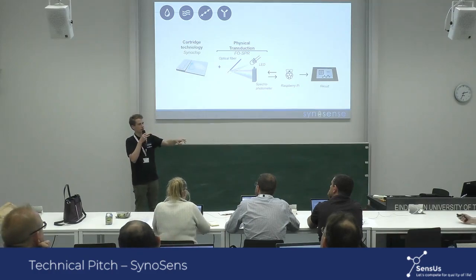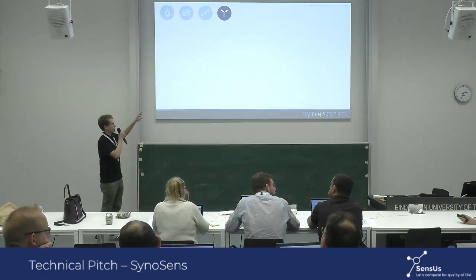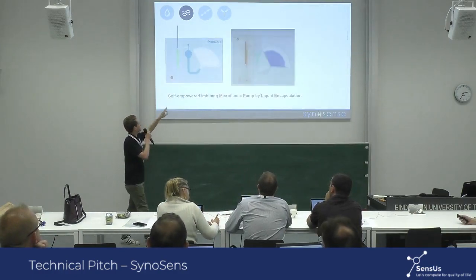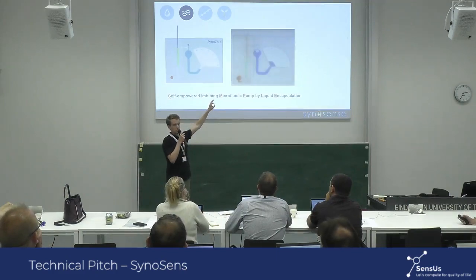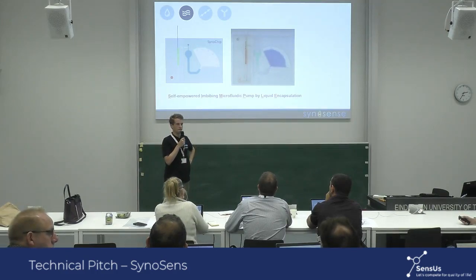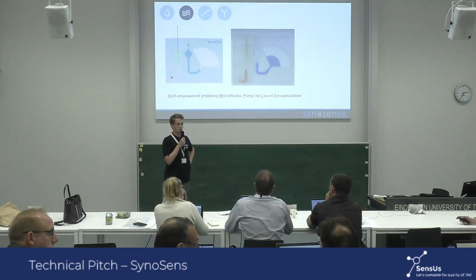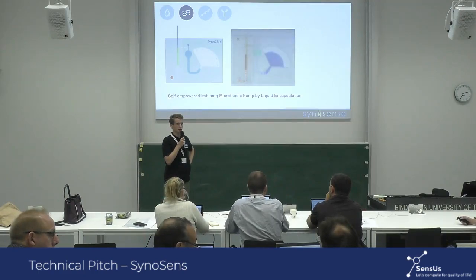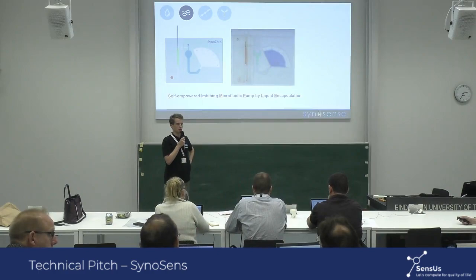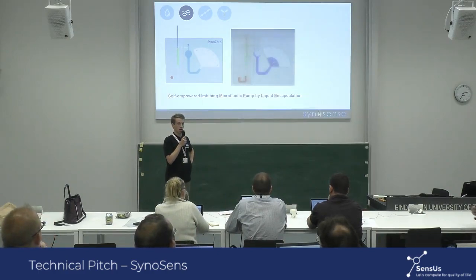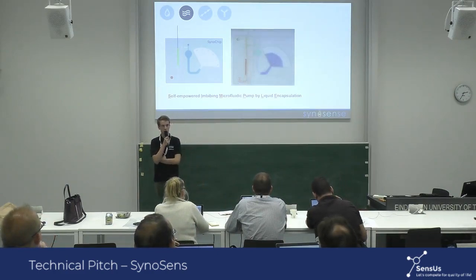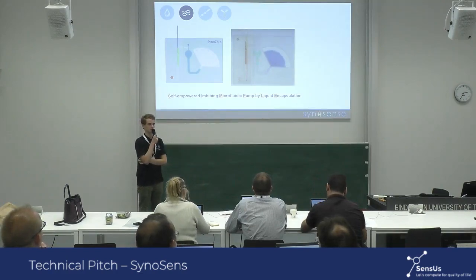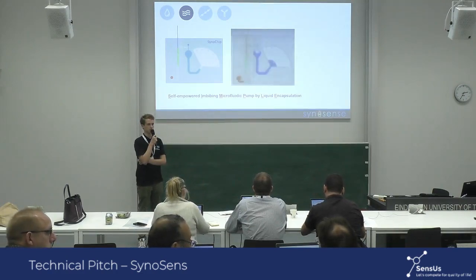But actually, if you could go back to the microfluidic slides, you can see that our chips are designed in such a way that they can take this washing step. Like the green fluid you will see there, this is a washing step. But is that a washing step at what stage? Because normally what you do is first you capture your adalimumab, and then you wash off excess. That's not necessary. Okay, that means that your assay might be sensitive to a high dose hook effect, meaning that if you have a high excess.